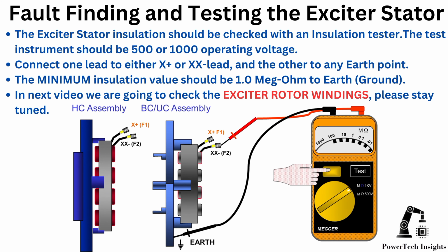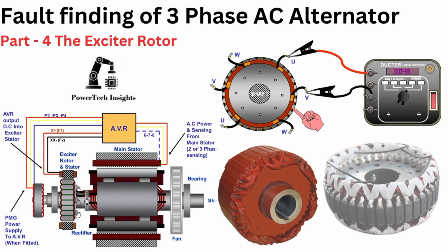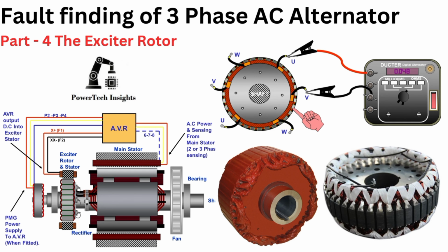The exciter stator insulation should be checked with an insulation tester. The test instrument should be 500 or 1000 operating voltage. Connect one lead to either X plus or XX lead and the other to any earth point. The minimum insulation value should be 1.0 megohm to earth. Part 4. The exciter rotor. In this part, we will provide a comprehensive guide on fault diagnosis for the exciter rotor.